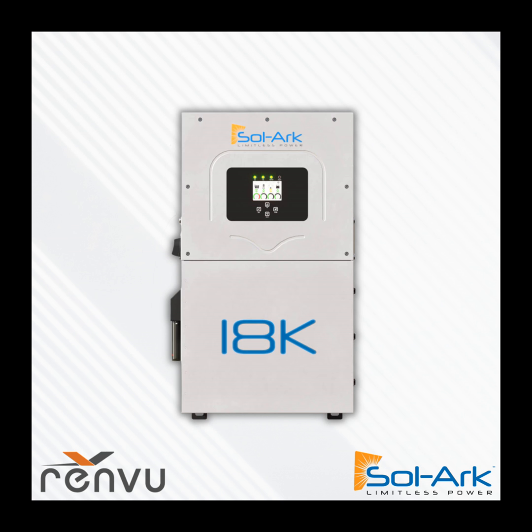The 18K can accommodate larger solar arrays, but it is fundamentally a larger inverter than the 15K. The nameplate on the battery for the 15K is 12 kilowatts; the nameplate on the 18K is 18 kilowatts. While the continuous output power under the right circumstances is only a little bit more, the surge capacity -- that less than 1 second load needed to start up air conditioner units, multiple air conditioner units, etc. -- is 50% higher on the 18K than on the 15K. So if the customer has multiple central air conditioner units, as solar customers are wont to do in Texas in particular, you can design with confidence a system using a single inverter adequate for that 200 amp service.